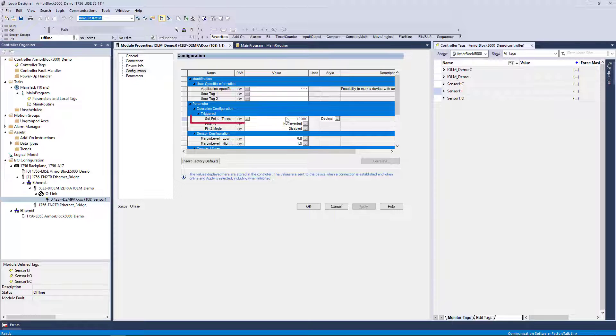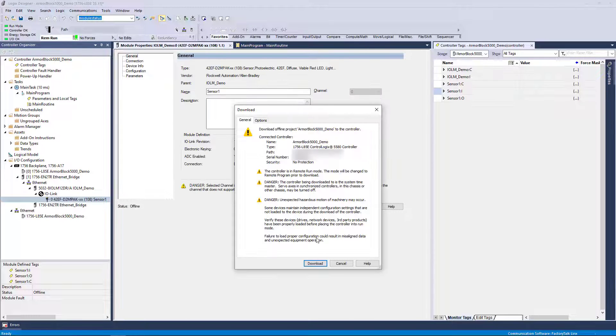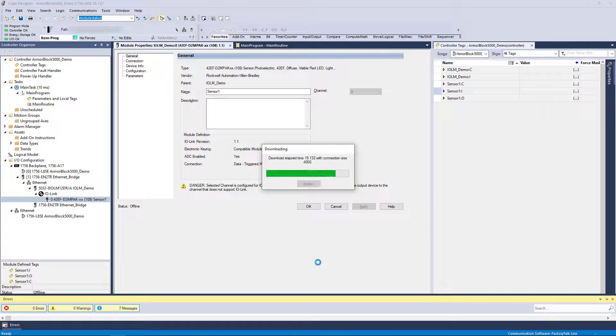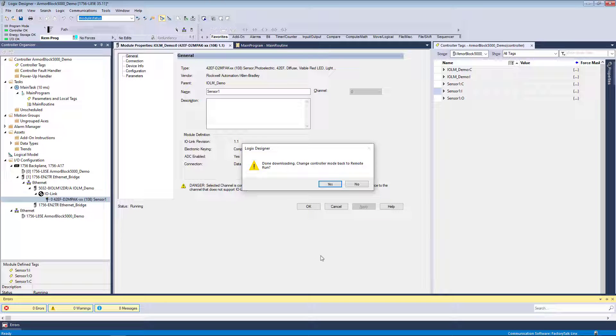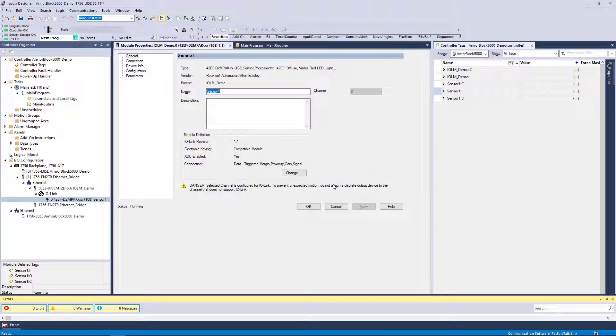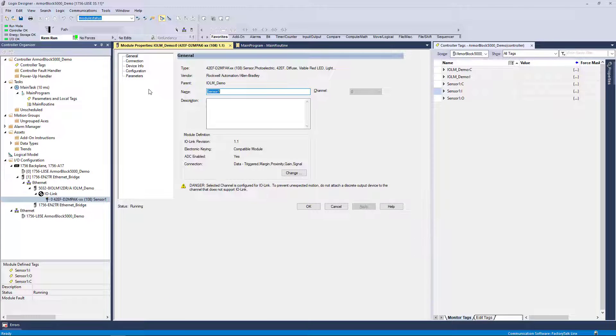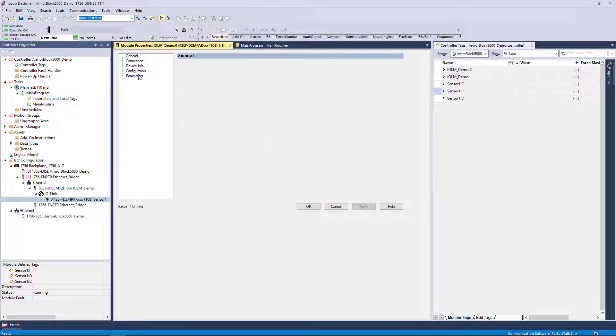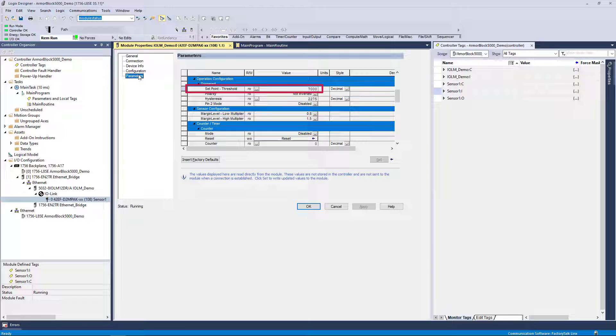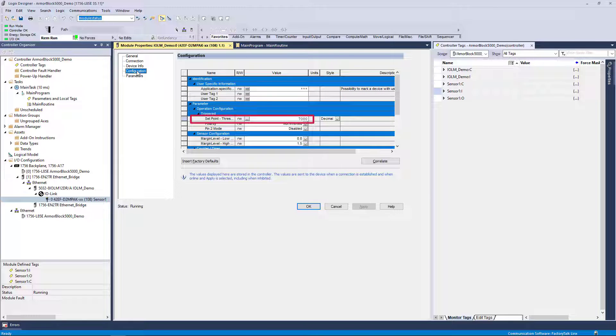We will go offline to make a change and then download the project. Once the download completes, you can see that the change was pushed to the IO-Link device because the controller is the main storage location of the configuration. Observe that the value of 7000 on the Parameters tab matches the configuration tab value.